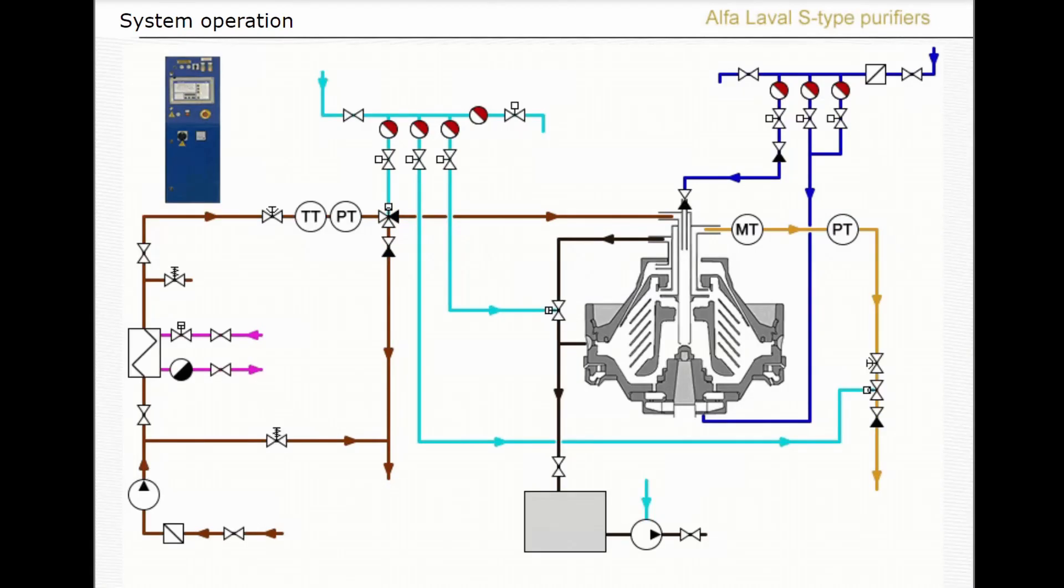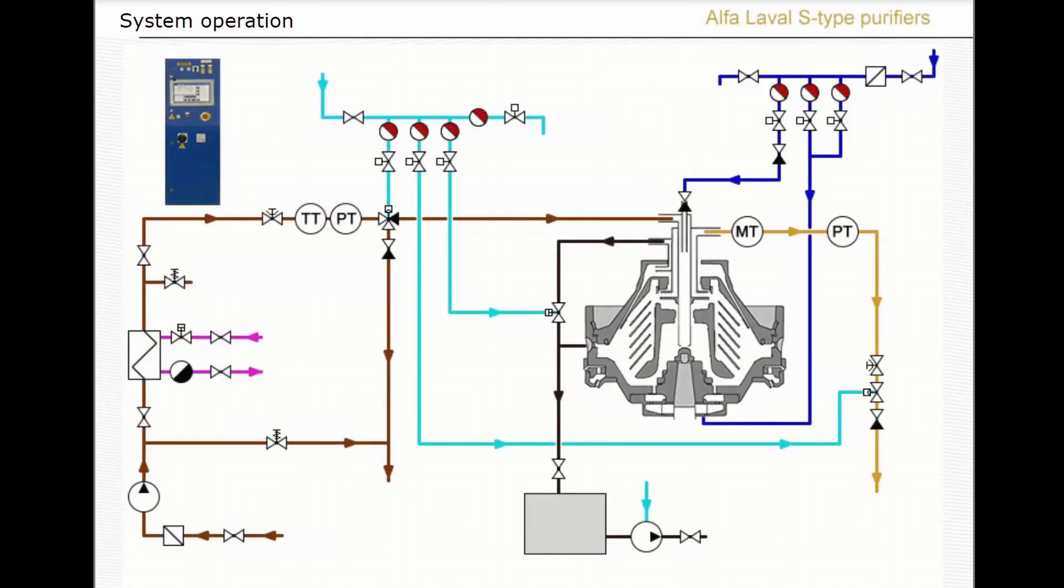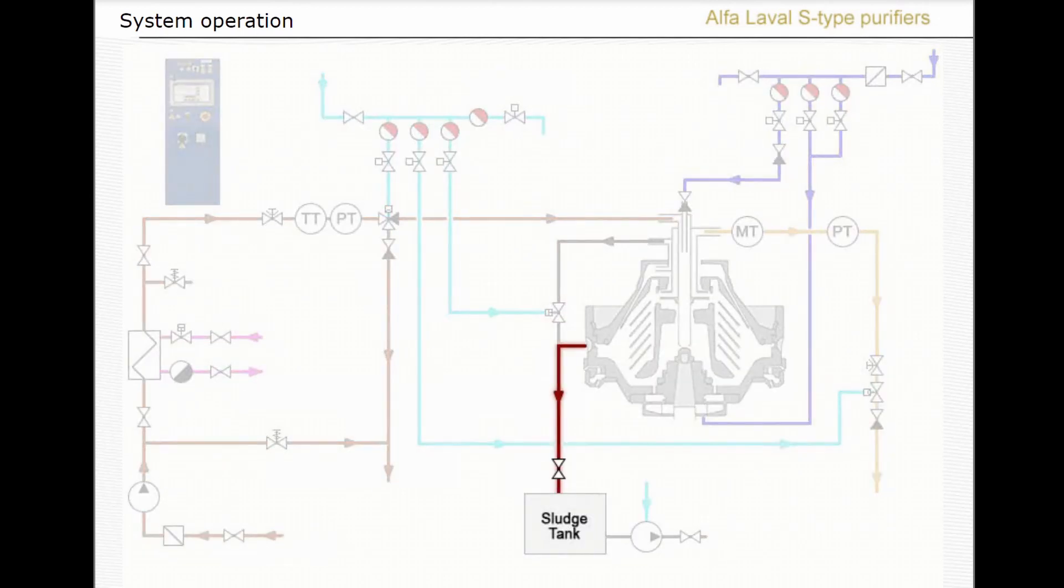Oil cleaned in the separator flows to the heavy fuel oil service tank. The water transducer continuously measures the water content in the cleaned oil and the regulating valve controls the back pressure in the clean oil outlet. Discharge of sludge and water from the bowl takes place at preset time intervals and the sludge exits through the discharge line.